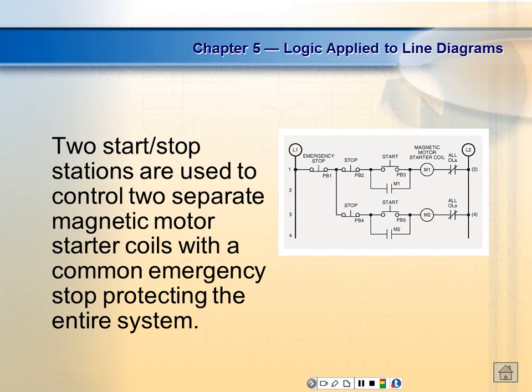So as long as they're pushed down, they'll remove power from the control circuit. We have to remember, if we've got e-stops, it's got to be in everything, right? So normally what we do is we use the e-stop button to de-energize a relay by itself, and then we put that contact in all the runs. Or we put the contact in the line, L1 side. So both of those are very popular too. And then put everything else down below that.